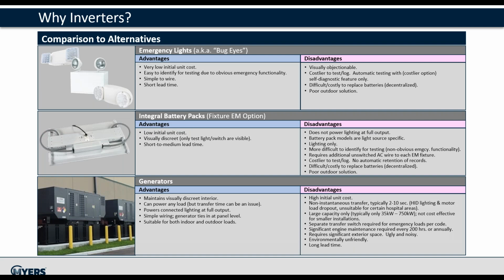If a generator serves both emergency and non-emergency loads, a separate transfer switch and emergency panel is required. There is significant engine maintenance. It requires a large outdoor mounting space, is noisy, unsightly, and environmentally unfriendly, and generally has longer lead times.